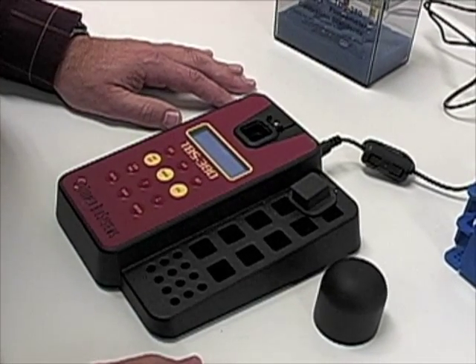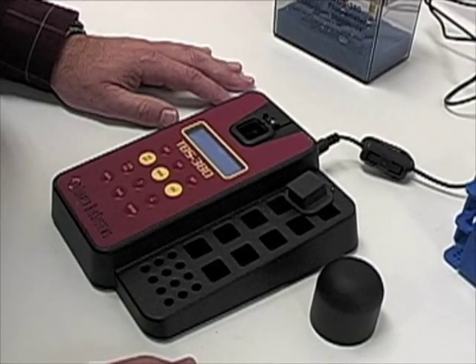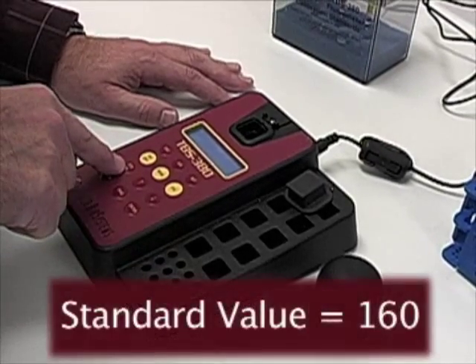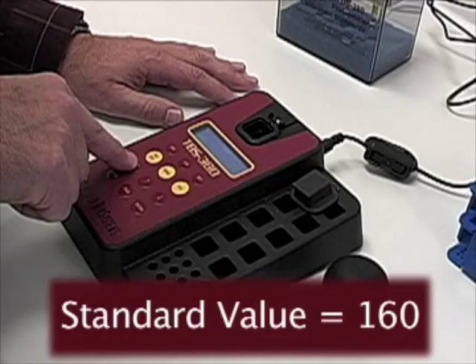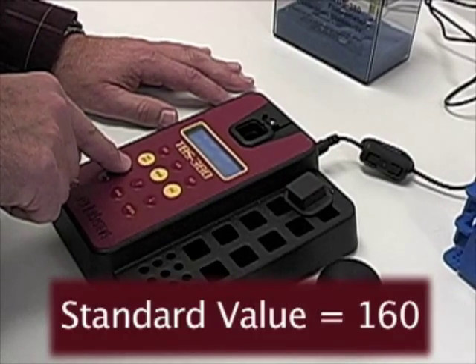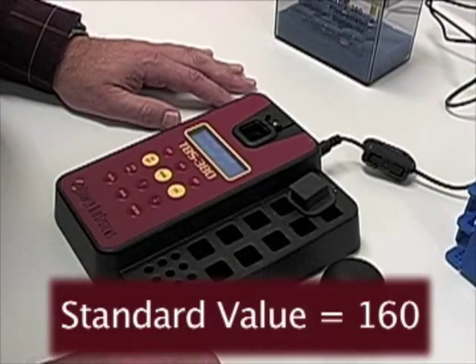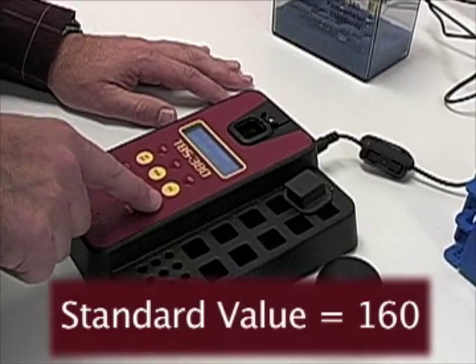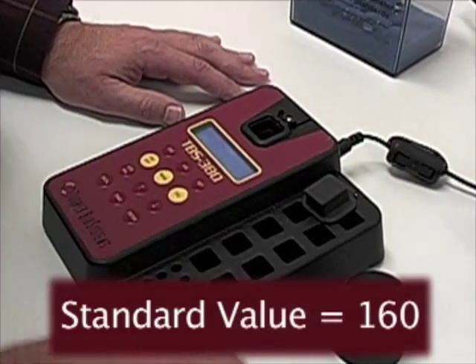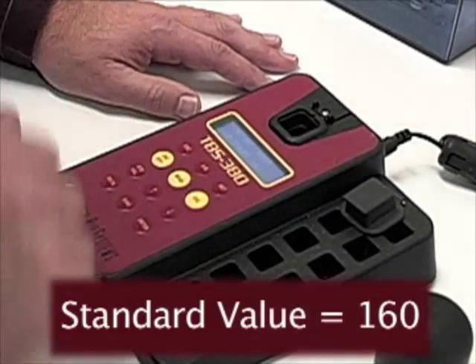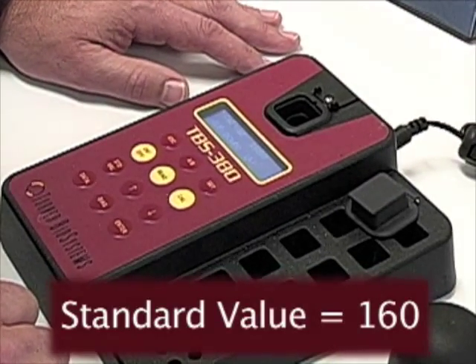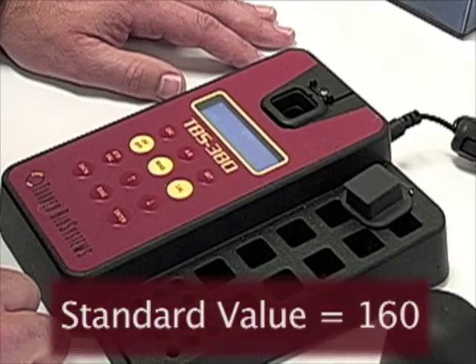The next thing to do to calibrate the instrument, you want to make sure that the standard value is the correct value. It should be 160. You can use the up and down arrows to change that value. Again, it should be 160. The memory retains the 160 setting.